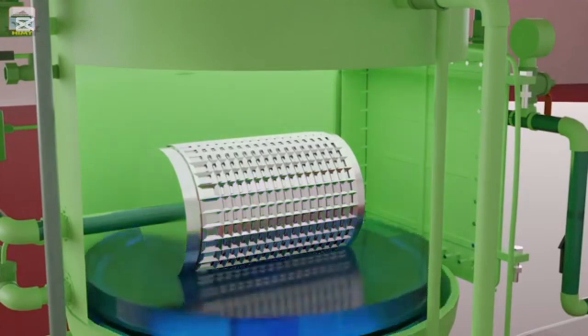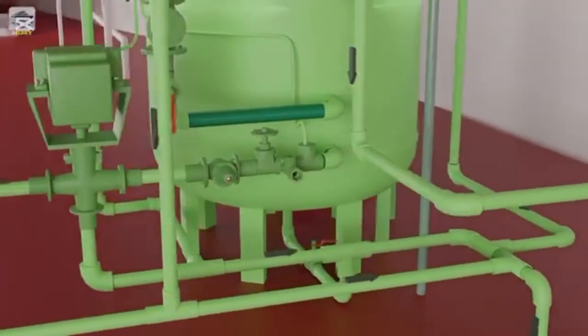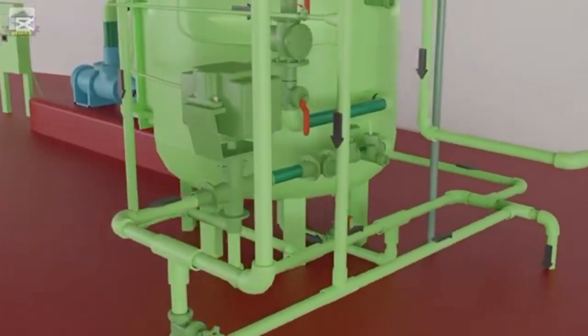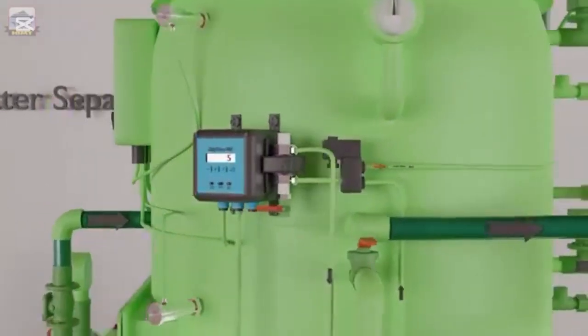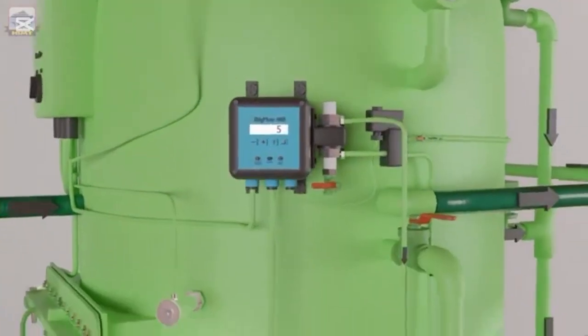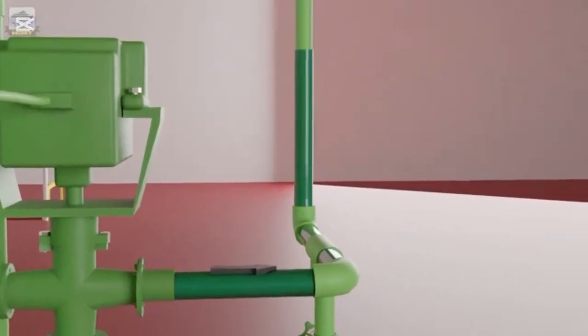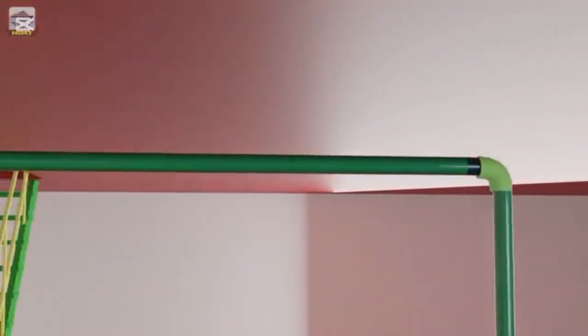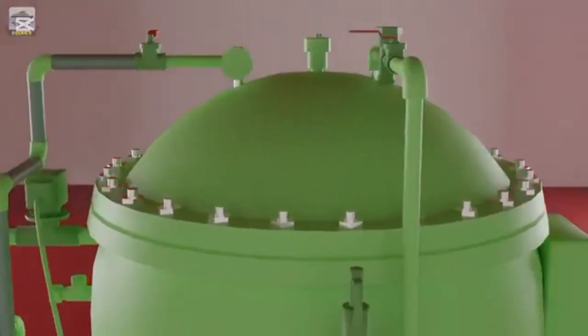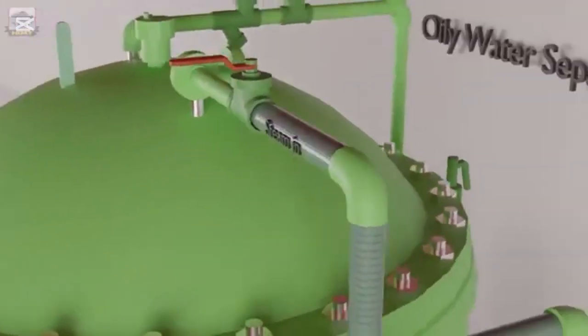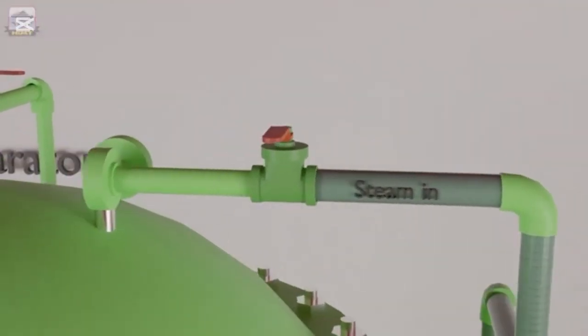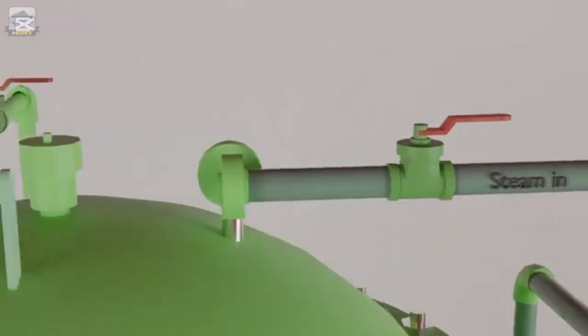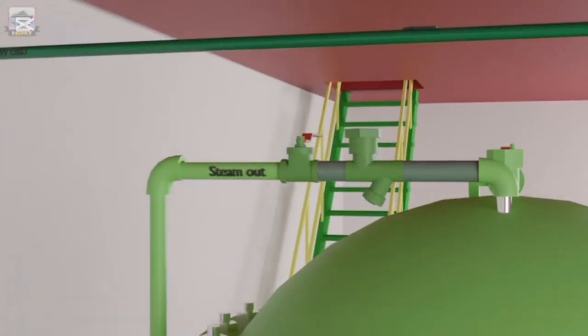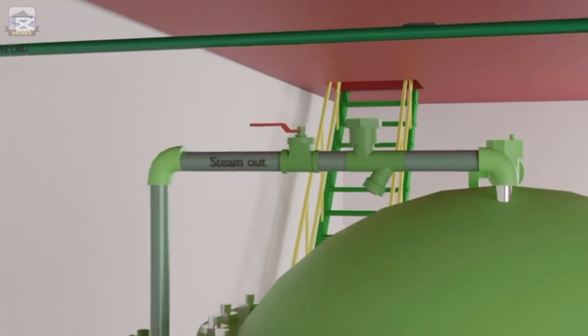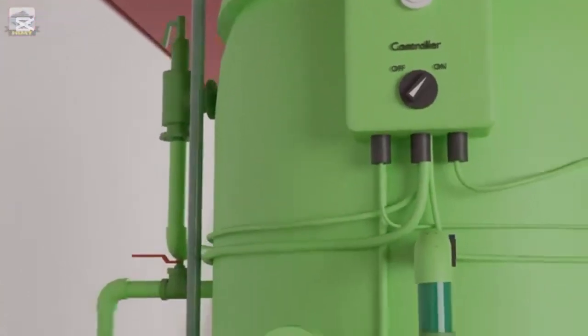Now, we'll trace the operation of the oil water separator. To operate the separator, first open the seawater inlet valve. Next, open the bilge pump discharge valve. It's followed by opening the secondary chamber outlet valve. From the secondary chamber, water exits through the three-way valve to the overboard line. When the oil content is less than 15 ppm, next open the steam inlet and outlet valves for heating.